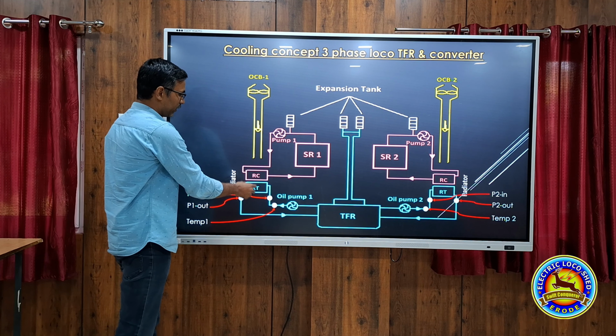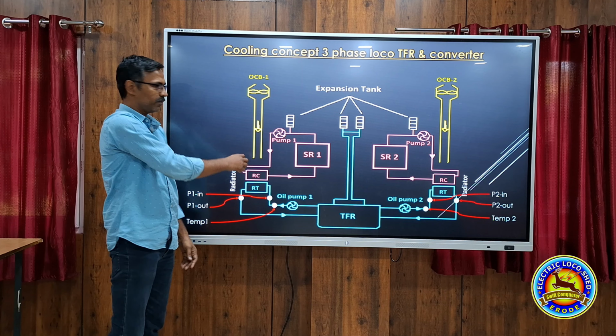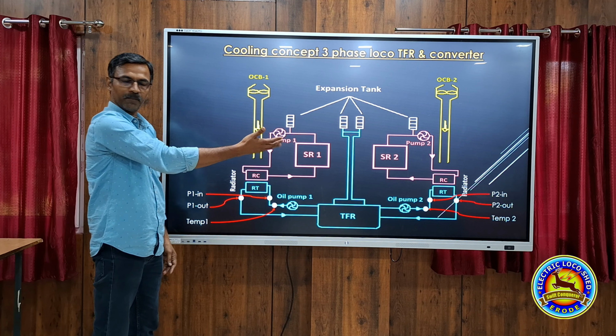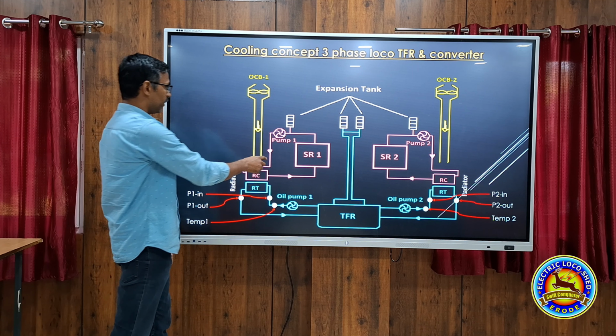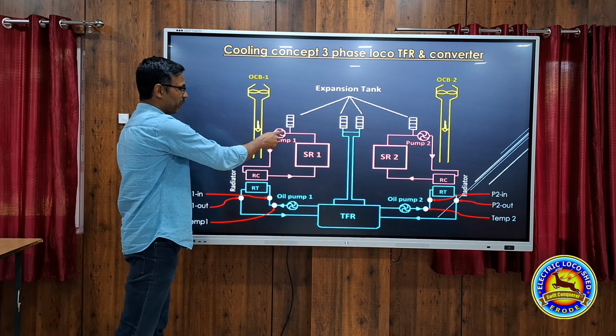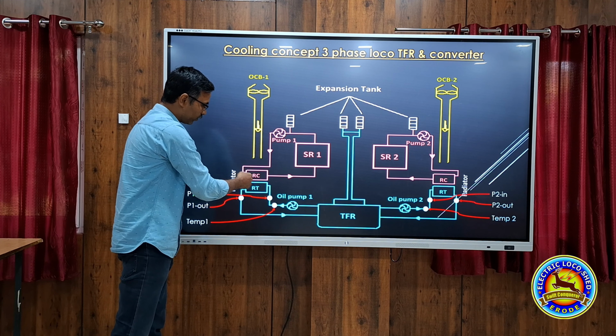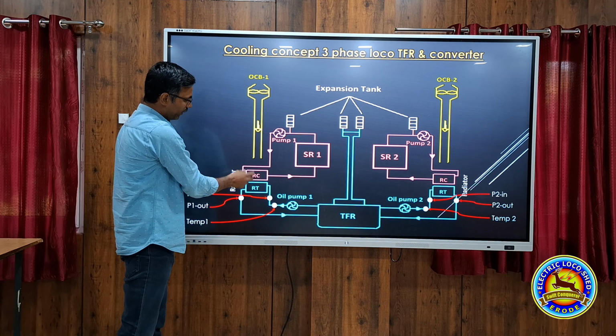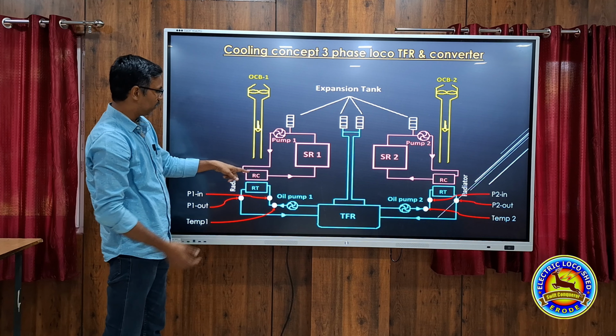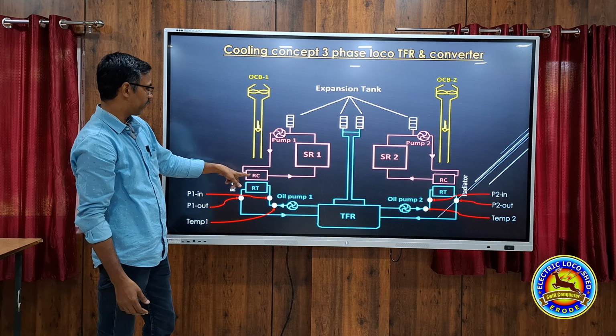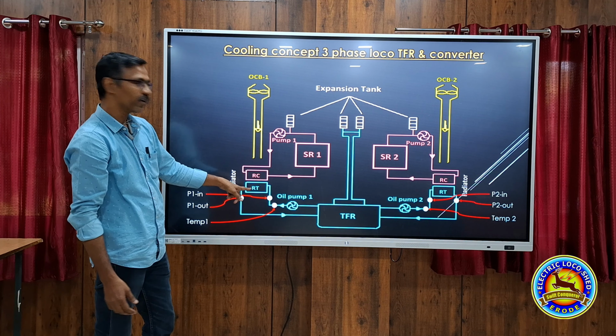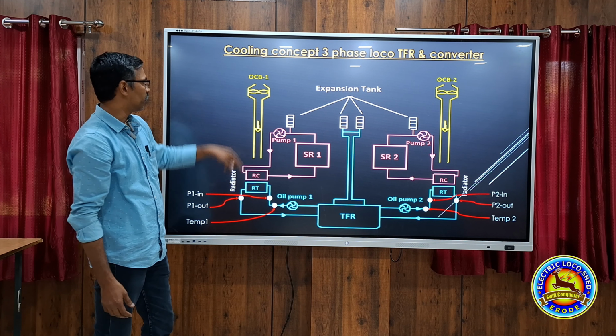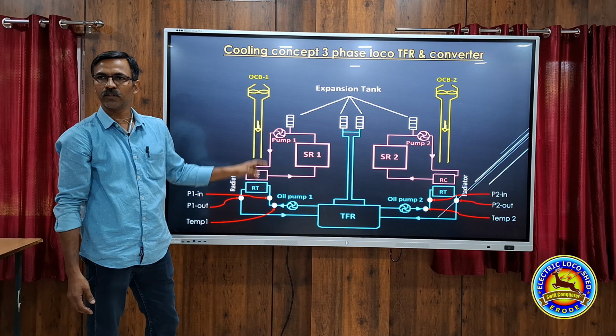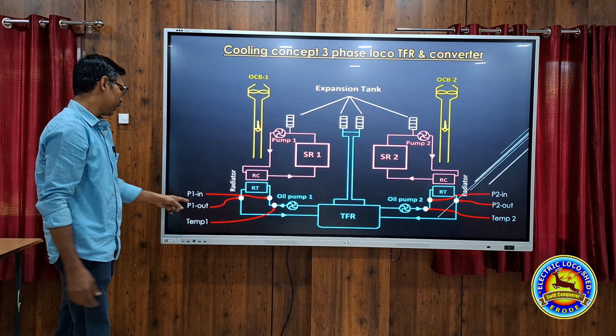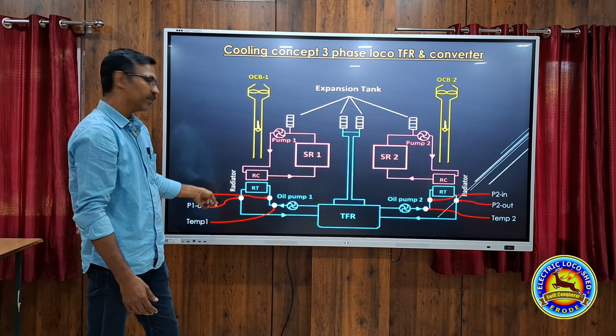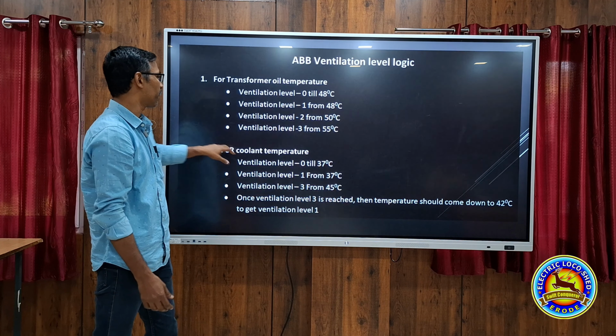That radiator is cooled by OCB1. The other side is exactly the same, there is no difference. For the SR, one pump is there. It will circulate the coolant through the radiator. The radiator is sandwiched type. The top radiator is for coolant, the bottom radiator is for transformer oil, and the same OCB cools both radiators. So these are the locations where the sensors are connected in the system.